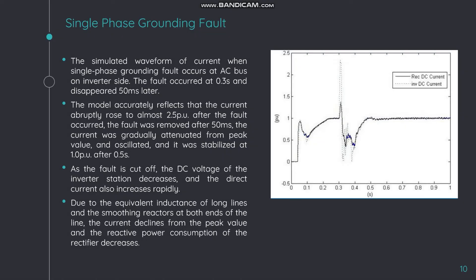A single phase grounding fault is introduced and compared with normal operation. The simulated waveform shows the current when a single phase grounding fault occurs at the AC bus on the inverter side. The fault occurred at 0.3 seconds and disappeared 50 milliseconds later. The model accurately reflects that the current abruptly rose to almost 2.5 PU after the fault occurred. As the current gradually attenuated from the peak value and oscillated, it stabilized at around 1 PU after 0.5 seconds. When the fault was cut off, the DC voltage of the inverter station decreases and the DC current also increases rapidly, with visible vibrations. Due to the equivalent inductance of long lines and smoothing reactors at both ends, the current declines from peak value and the reactive power consumption of the rectifier decreases.